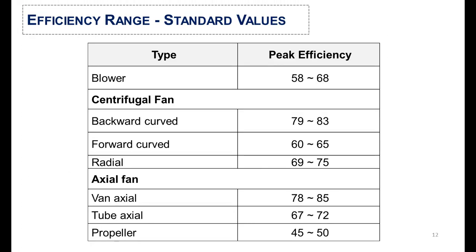Once we have calculated the efficiency of the fan or blower, we will cross-check it with standard values. For blowers, the peak efficiency value is from 58 to 68%. For centrifugal fans it varies from 60 to 83%, and for axial fans it varies from 45 to 85% according to their impeller design.